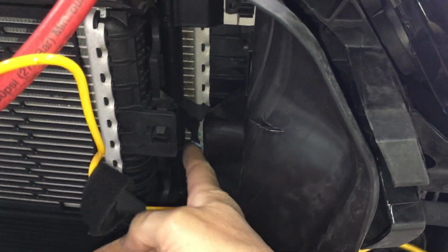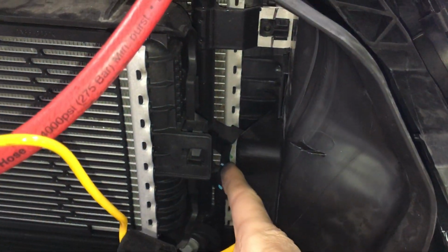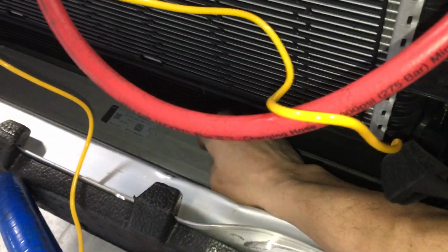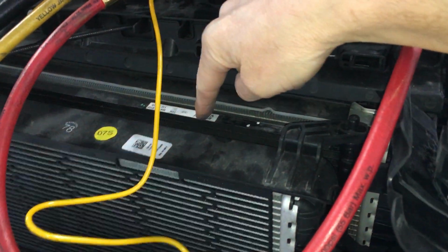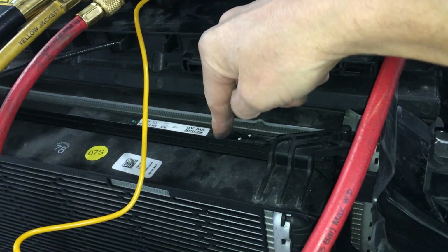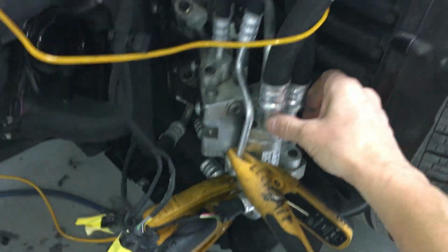Okay, so we're cold coming out. It goes back behind this. It's not this one here. It's actually going back on a bar, back to the condenser right here. Here's another heat exchanger right here. Here's another heat exchanger right here. And then behind this is the radiator right there, and then condenser right there. So I'm going to put it in a different mode and see if I could swap this around and get some normal readings here.